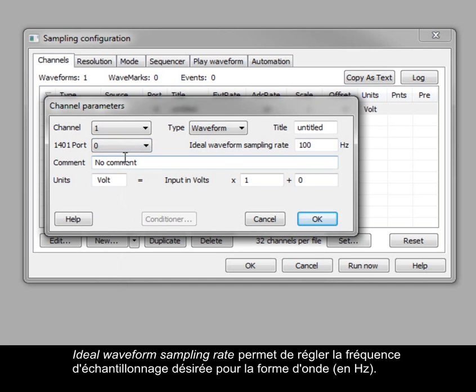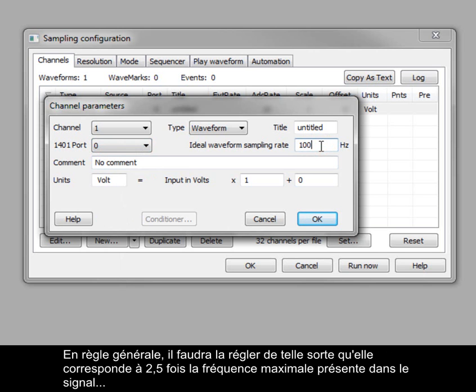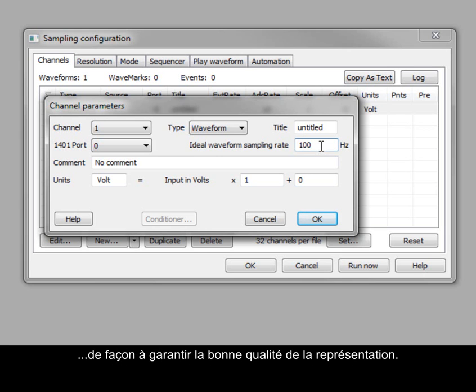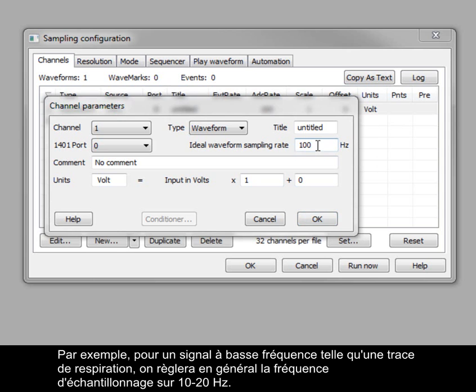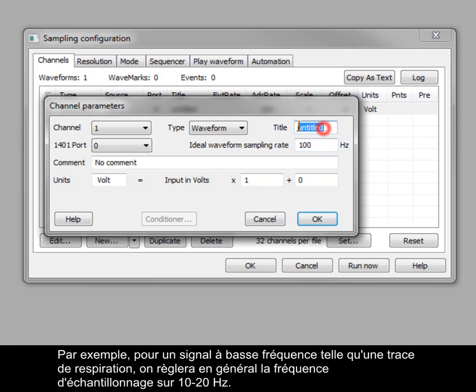The ideal waveform sampling rate sets the desired sampling rate for the waveform in hertz. As a general rule, this should be set to two and a half times the maximum frequency present in the signal to produce a reasonable representation. For example, a low frequency signal, such as a respiration trace, would typically require a sampling rate of 10 to 20 hertz.